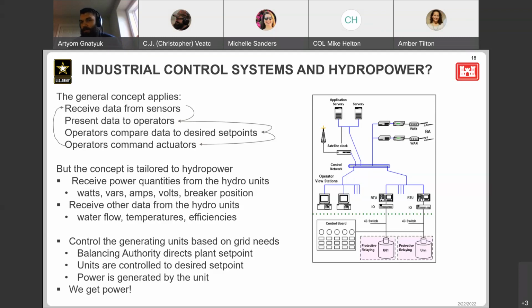A big piece of industrial control systems in hydropower is based on grid needs. It's not just an operator saying we're generating, say, 50 megawatts at this plant, that's good enough. It's really dependent on what the electric grid needs. Do we need to generate more or less power? Are there more loads coming on, motors coming on or off? Based on that, the balancing authority will direct the project to a set point, telling the operator we need 100 megawatts this hour because of a huge load coming online that we have to support.